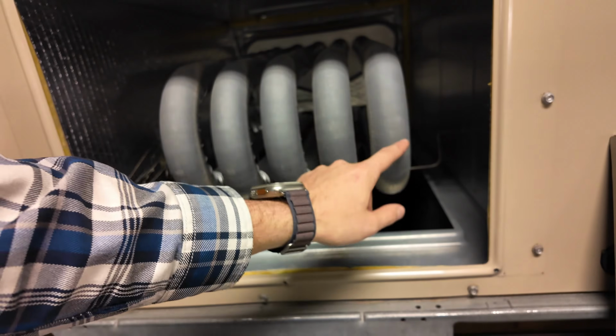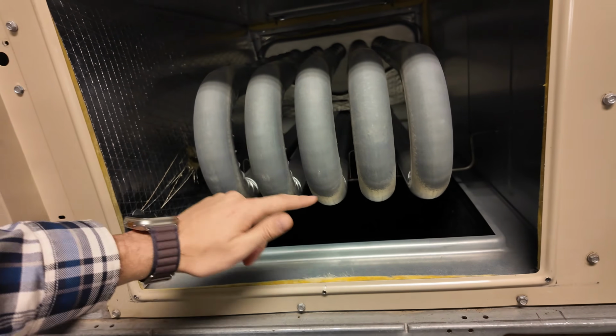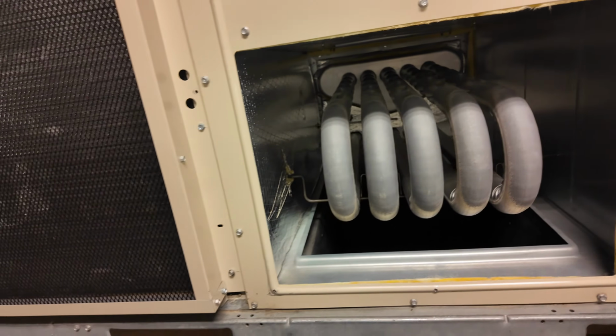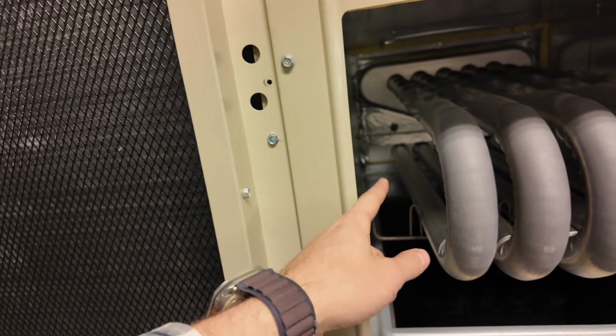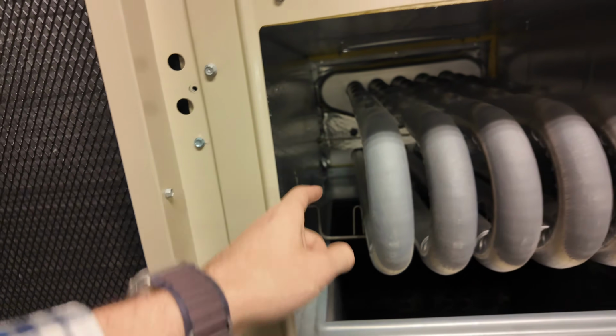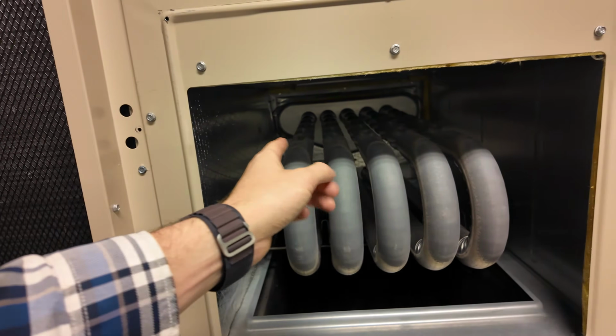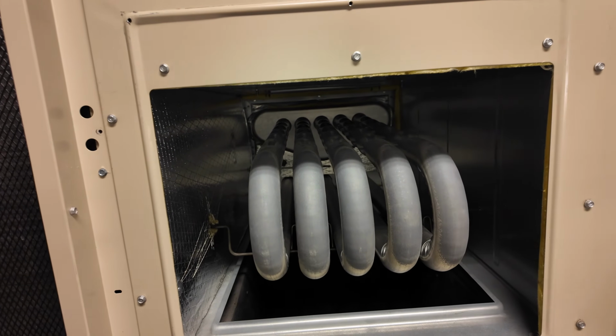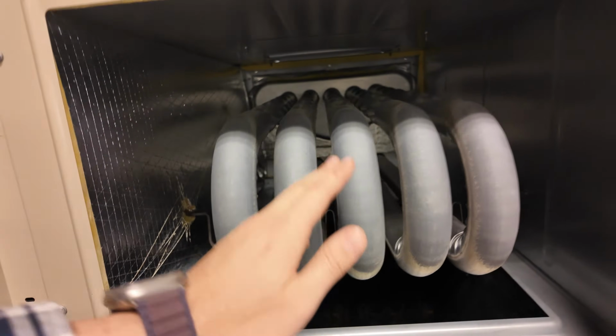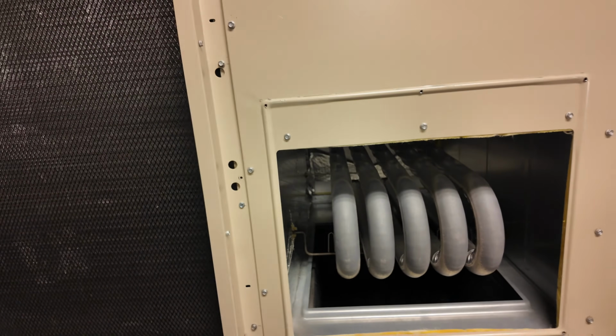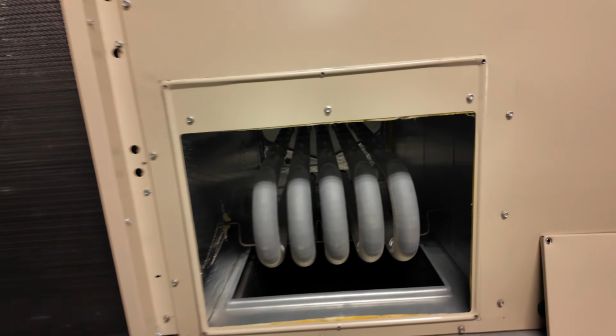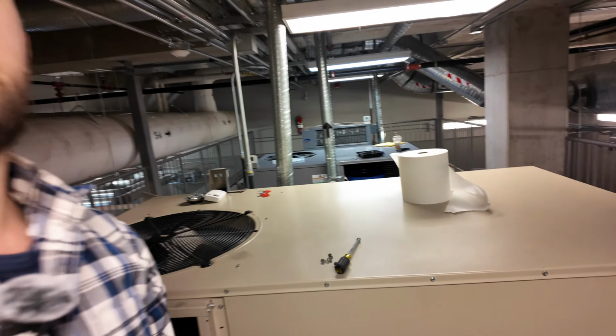And you'll find on the Lennoxes, they crack here 90% of the time, somewhere on the U-bend. I haven't seen many cracks down there at the start, and not very many up at the pitch points area. But I've seen numerous cracks right here. So if you're going to look for a heat exchanger crack, those are my two recommendations. It doesn't take very long to check for it. You get a good flashlight, take the panels off, takes you about 30 seconds. And it's a good thing to check.